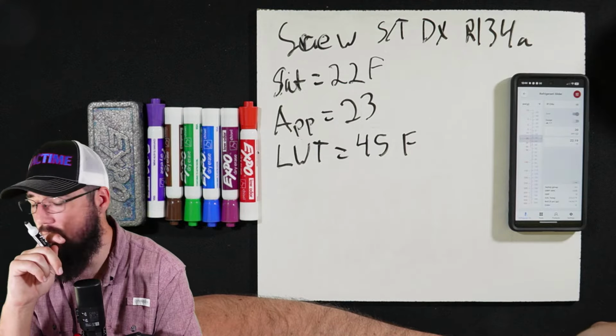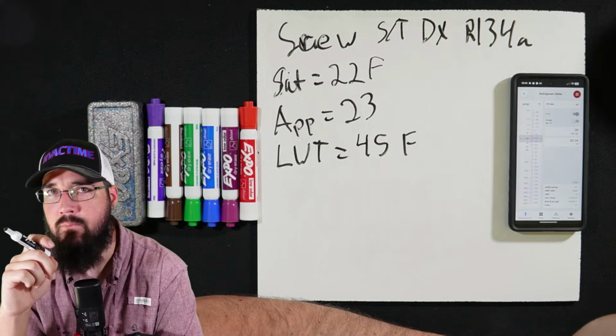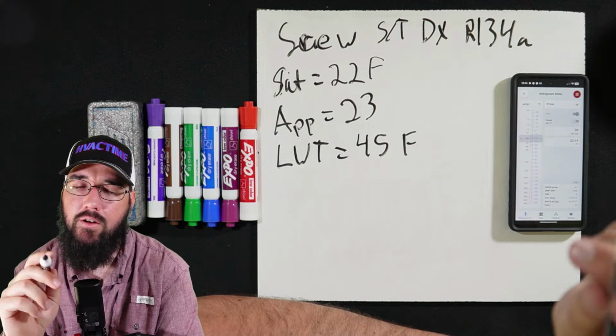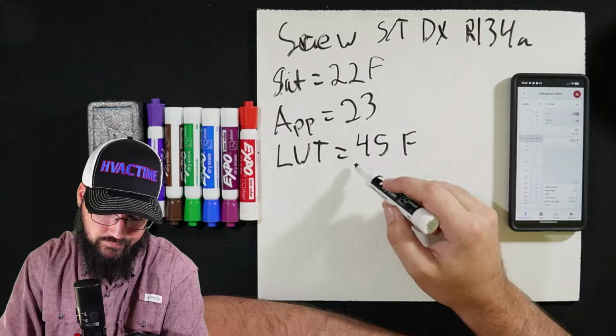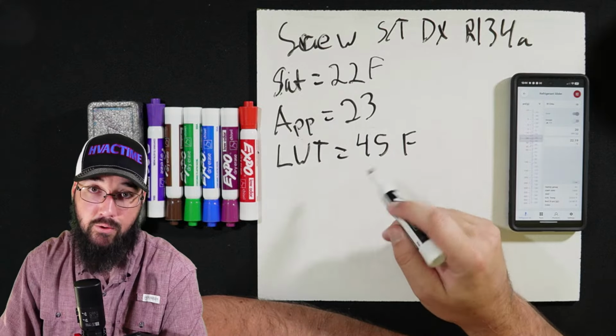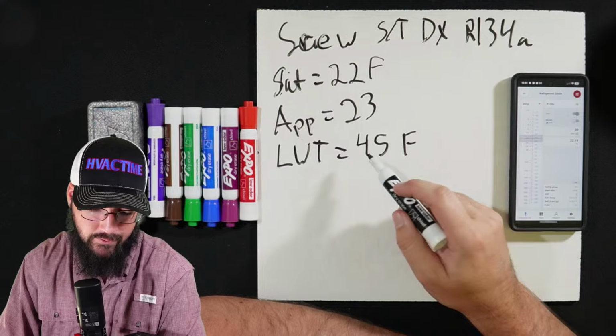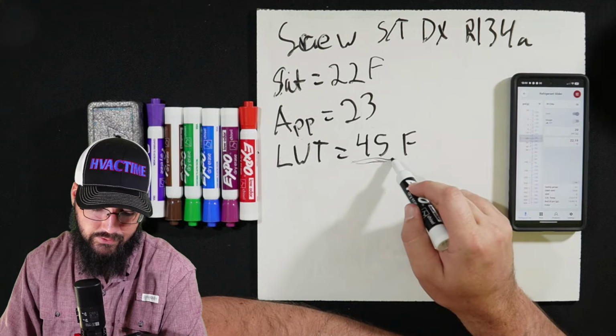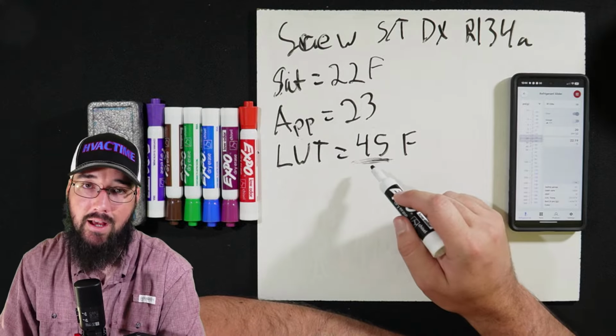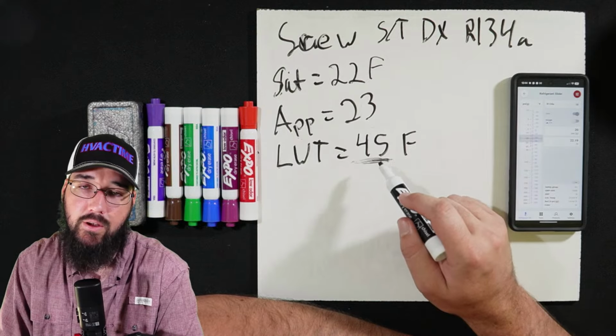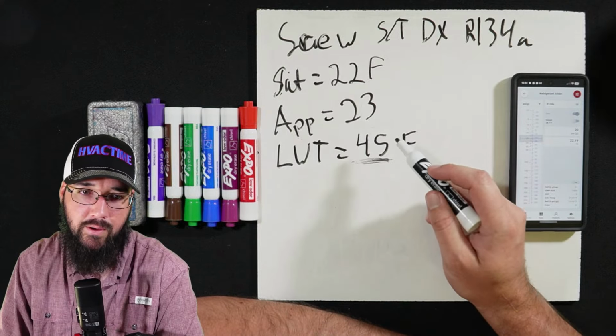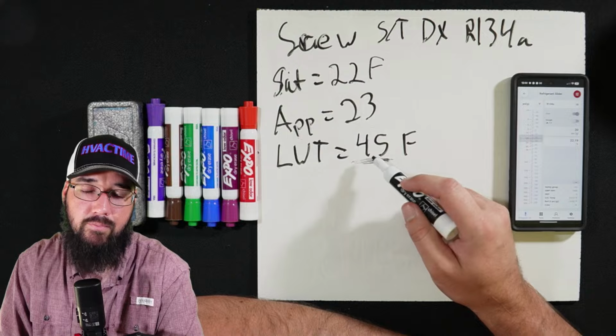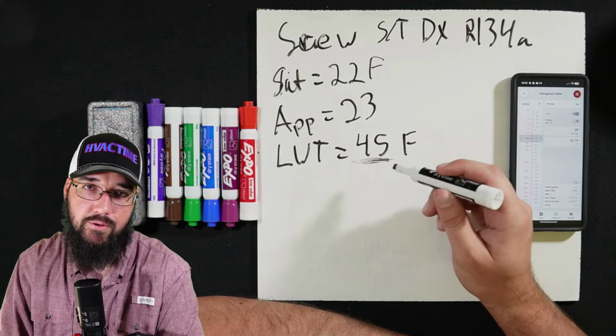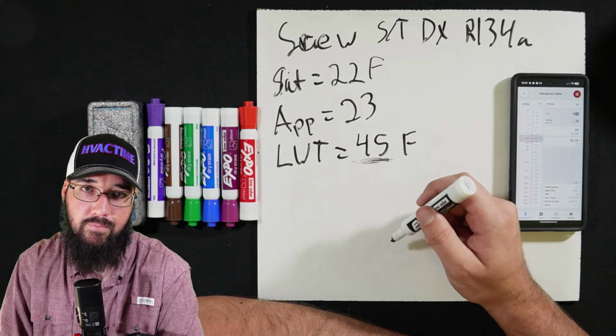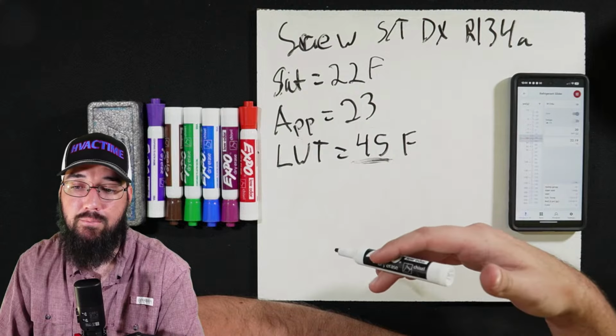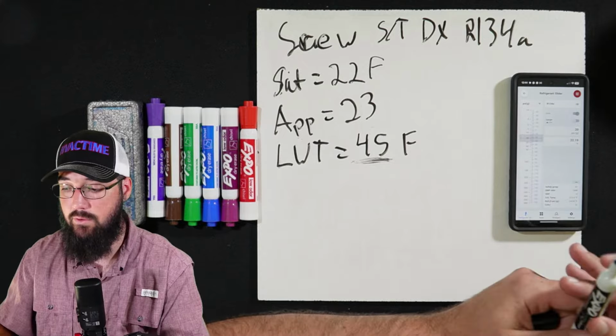Because if it was a low load, see, here's the thing. If it was a low load issue and we don't have enough heat coming into the chiller, we should not be at this high of a leaving water temperature. You said we're right at or just above set point. That wouldn't be true. We would see this leaving water temperature much lower. And we would get down closer to the possible trip point for that leaving water.